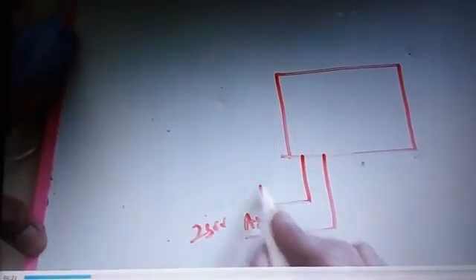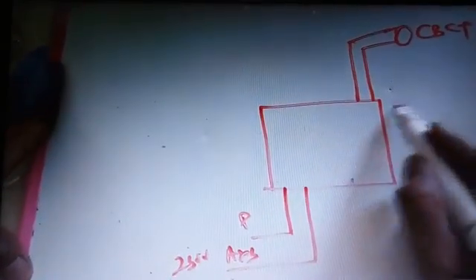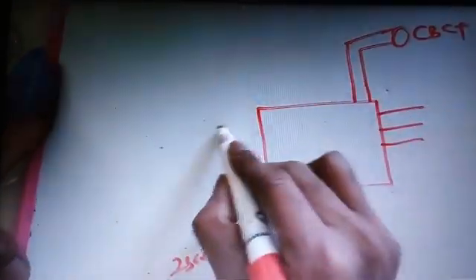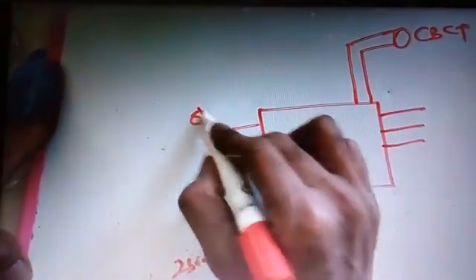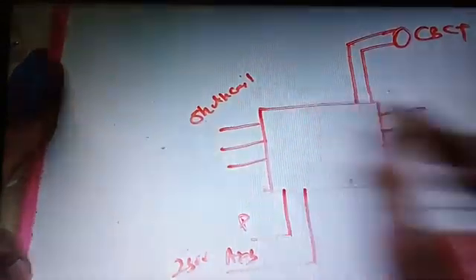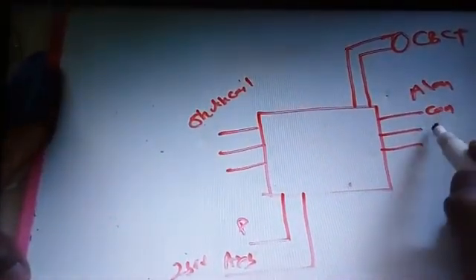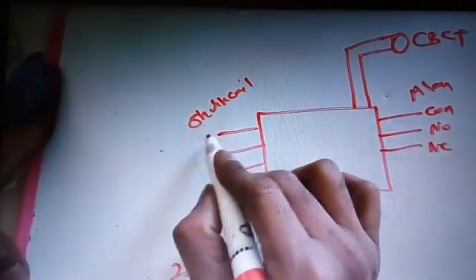Now we are going to see the ELR connection. The ELR has two terminals for auxiliary supply, that means 230 voltage AC. Here we are going to see two terminals for the CBCT arrangement. Then we have two relays. Generally a relay has three terminals. One relay is for shunt trip or tripping coil. Another one is for alarm. So two relays have two common and two normally-open points.